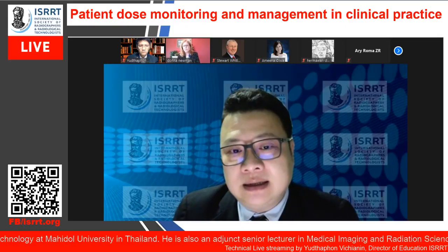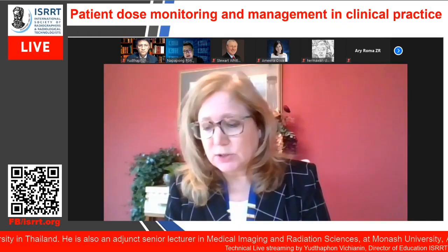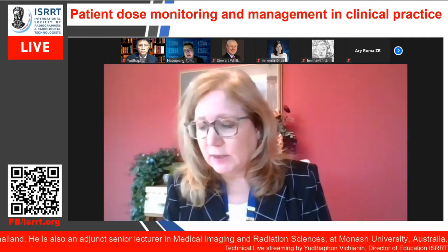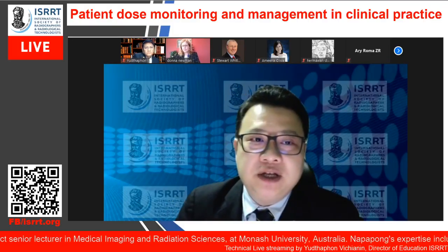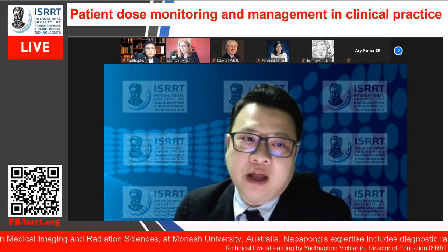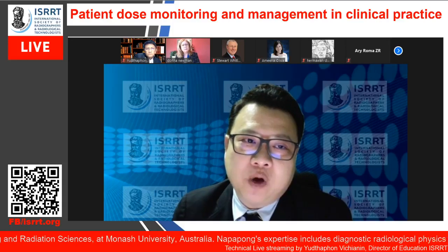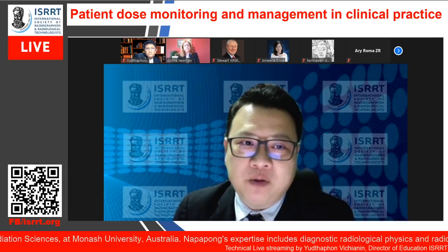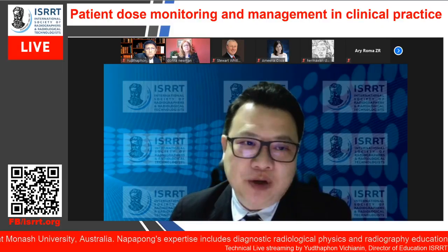And then now to a more technical question again. What are the main reference parameters to measure for the dose, CTDI volume or DLP? See, for dosimetry, patient dose in CT is DLP, dose length product, because dose length product means you multiply CTDI volume, which is the dose that is exposed to a slab of tissue from one collimation, multiplied by the length of the scan. So the absorbed dose to the patient.